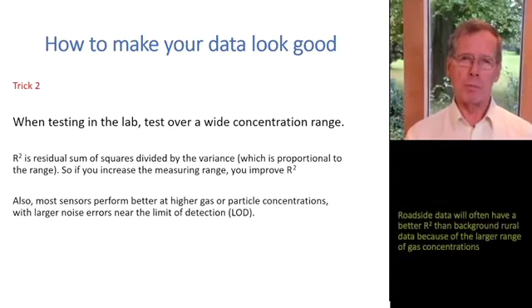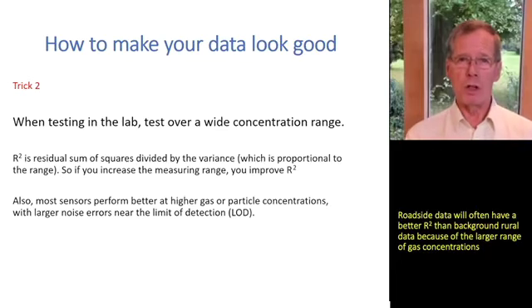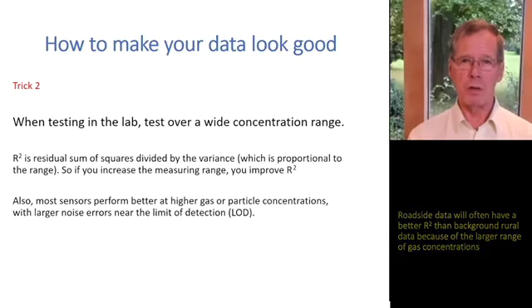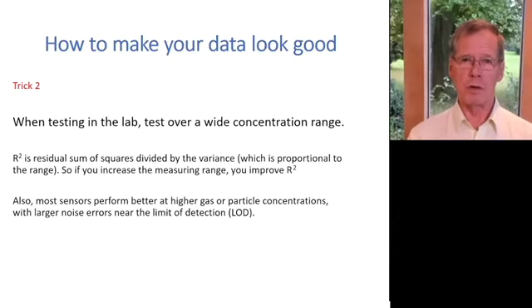Most sensors operating at really low concentration ranges — we're talking about low parts per billion of gas concentrations and under five micrograms per cubic meter of air quality particle densities — when you're looking at these low levels, you start to approach the signal and noise level of your sensors and your sensor electronics. When you're working down there, you'll get higher errors just because you're working near the LOD.